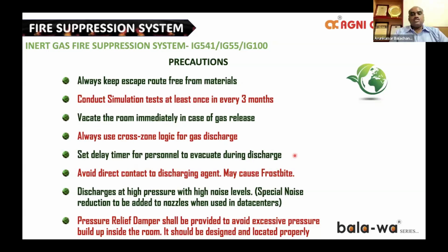Avoid direct contact with the discharging agent as it may cause frostbite. Since it's a nitrogen-based system, direct contact will leave skin frostbite. And being a high pressure system, when the discharge happens, it also happens with high noise levels. So when the inert system is used in data centers, special noise reduction should be added to the nozzles to reduce the high level of noise so that the servers do not get affected due to the high decibel noise. And the most important thing is a pressure relief damper shall be provided to avoid excessive pressure buildup inside. These dampers or vents should be designed and located properly.